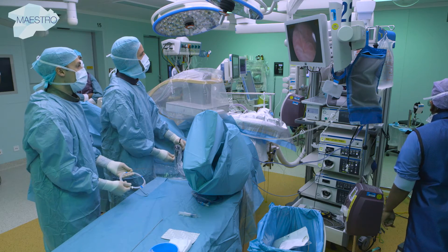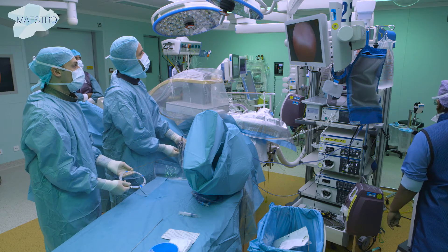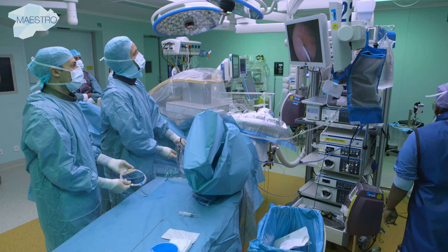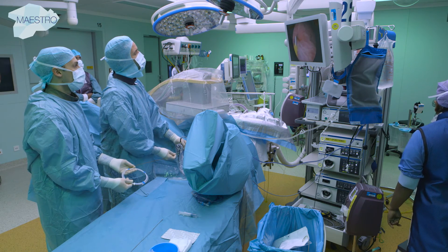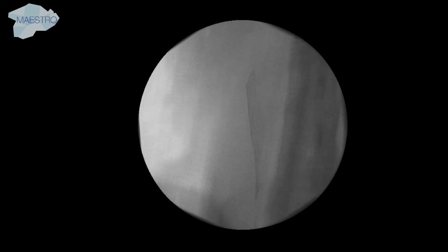Guide wires are most commonly 150 cm long with a diameter of 0.035 or 0.038 inches. When inserting the wire through the cystoscope into the ureter, sufficient radiopacity is necessary for precise placement of the guide wire.